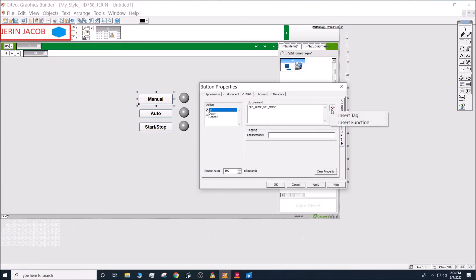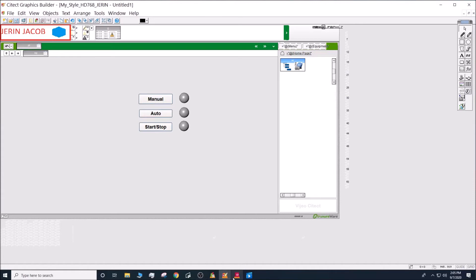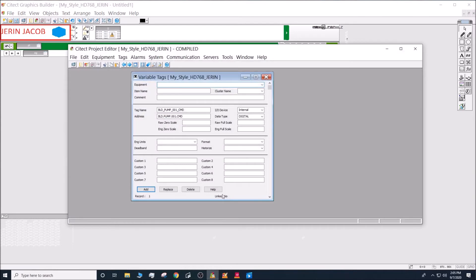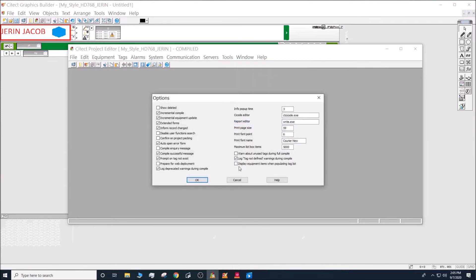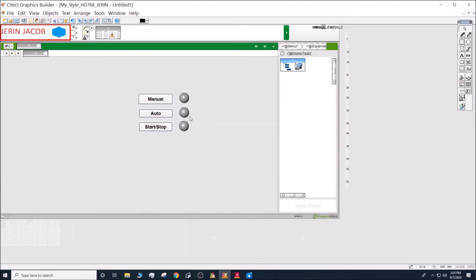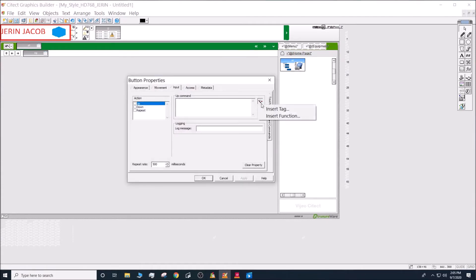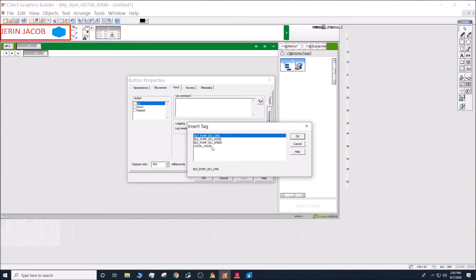If you don't see these tags when you click the magic wand, go to the SCADA project editor, then go to Tools > Options and uncheck 'Display equipment item when populating tag list' — it is checked by default. The reason is that we haven't created any equipment items yet; we'll cover equipment items in another video. Click OK and close it.